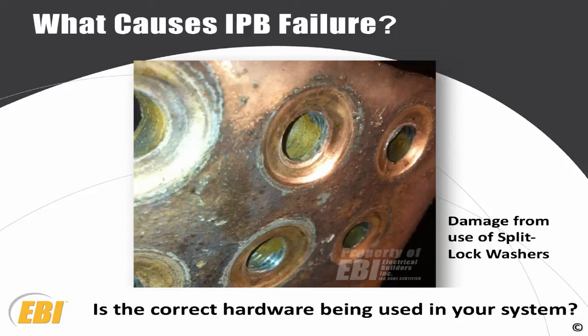Another big problem we have is using incorrect hardware on the bus connections. This picture shows damage from using split lock washers or from using locking nuts. What happens is the steel bolt will not expand as much as your aluminum conductor. Therefore, something has to give, and it's pretty much always the conductor. It will mash the flat washers up into the conductor itself. Plus, you also have something called material creep, where the conductor itself will be flattened out and spread out and will actually crack.